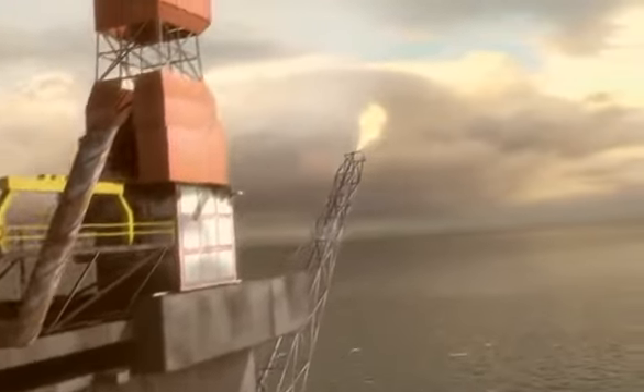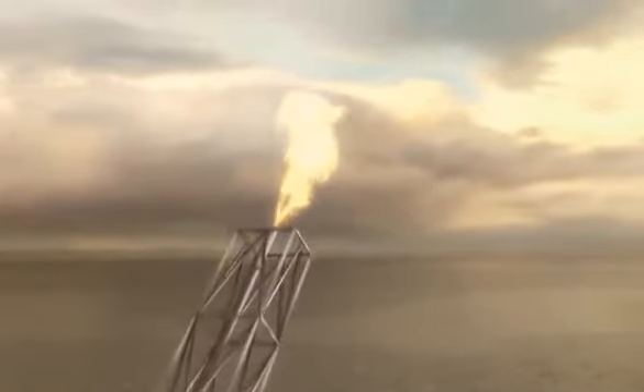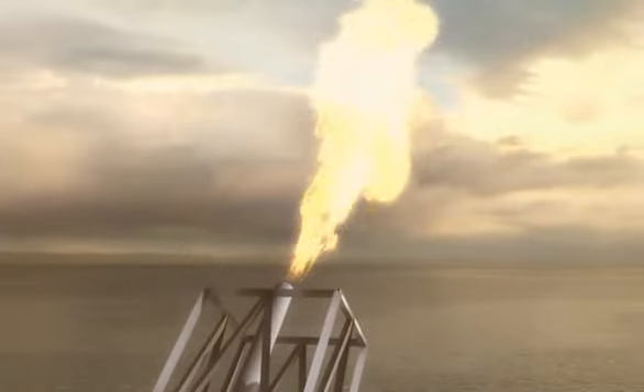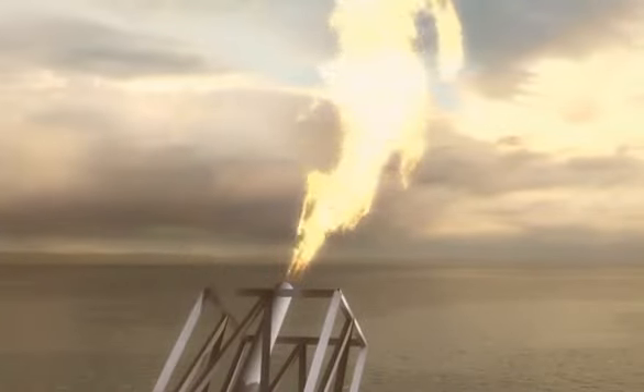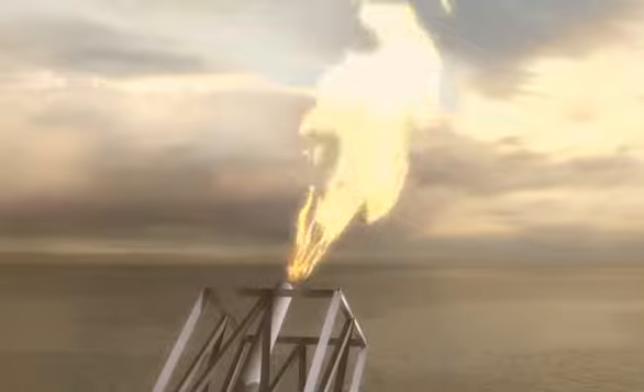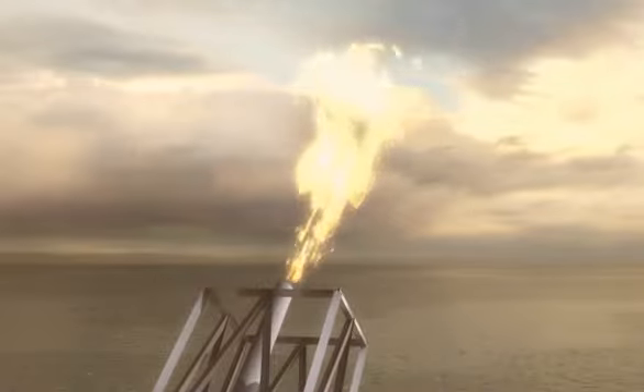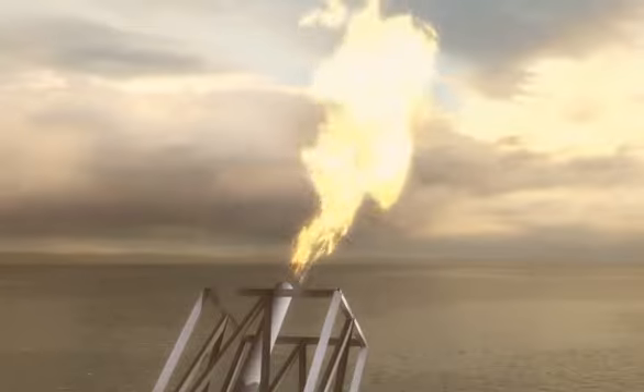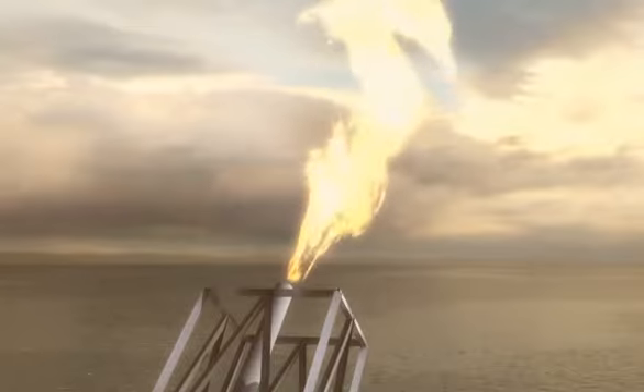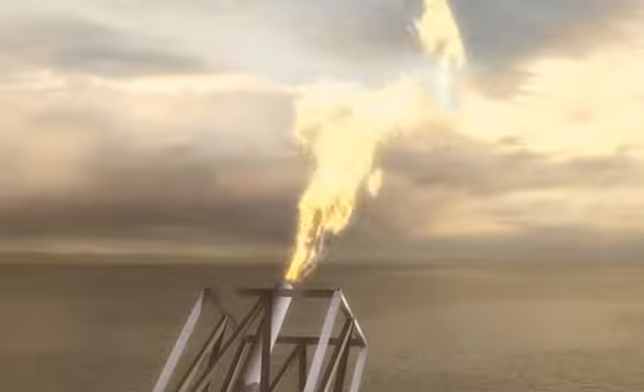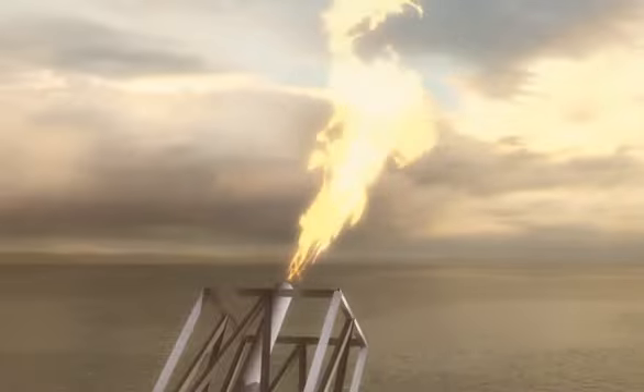In an environment where legislation and compliance requirements are forever changing, the accurate and reliable measurement of flare gas emissions has never been more important. Today, virtually every offshore production facility has flare gas meters installed to control mass balance, prevent leakage, and monitor CO2 emissions.